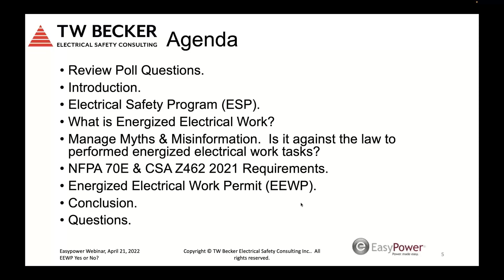So the introduction: in NFPA 70E Article 110.5, Electrical Safety Program, and CSA Z462 Clause 4.1.7, the employer is supposed to have an electrical safety program, right? They're supposed to implement and document an overall electrical safety program that directs activity appropriate to the risk associated with electrical hazards. There's also a definition of what this electrical safety program includes - it's a documented system consisting of electrical safety principles, policies, procedures, and processes that directs activities appropriate for the risk associated with electrical hazards.